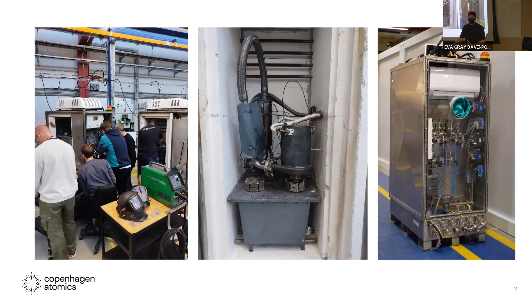This is one of these other systems doing filtration. One of the things we have inside the furnace is steel plates acting as a splash guard, because if something breaks, or the flange comes off and the pump empties all the volume in there in a few seconds, we don't want that going into the insulation. So we have a splash guard and a bucket at the bottom. Even though this has never happened, in principle it would deflect everything to the bottom without getting into the insulation, because there's inert gas on the outside. Whenever we've had a small leak on a flange or something, we just open up, scrape the salt off, there's really no corrosion, and we can run again, basically change the gasket and rerun.